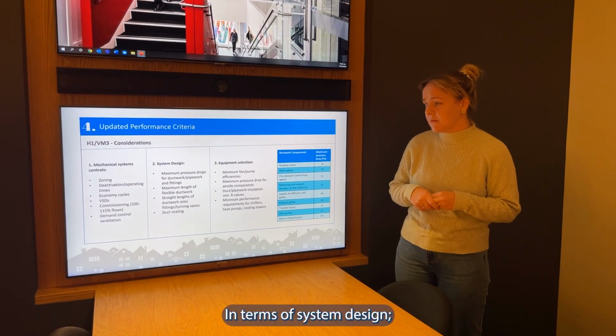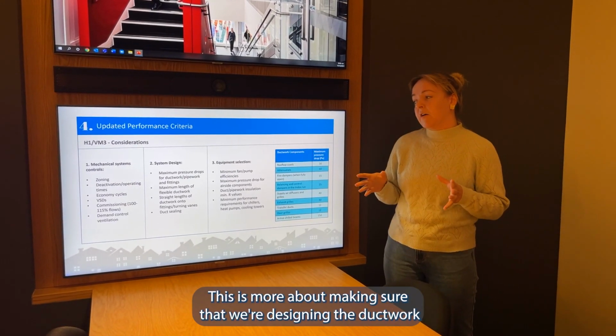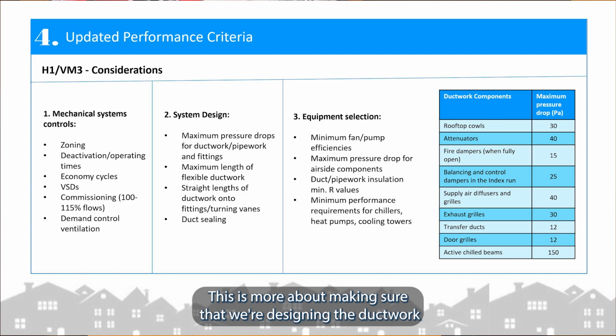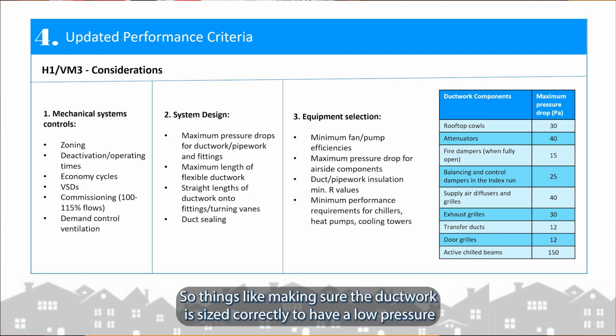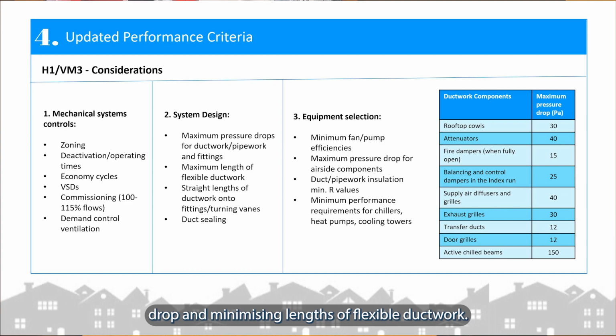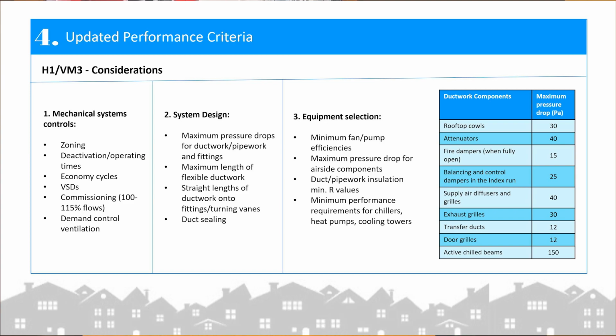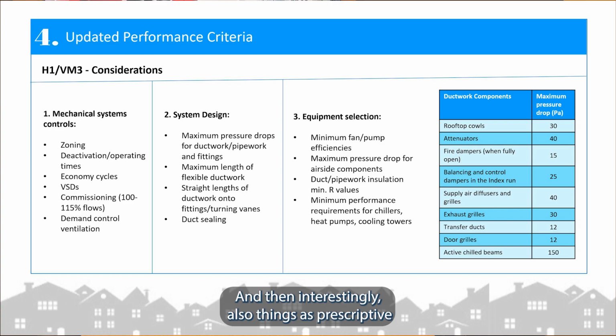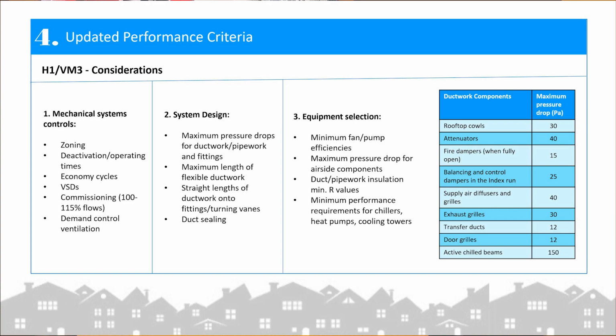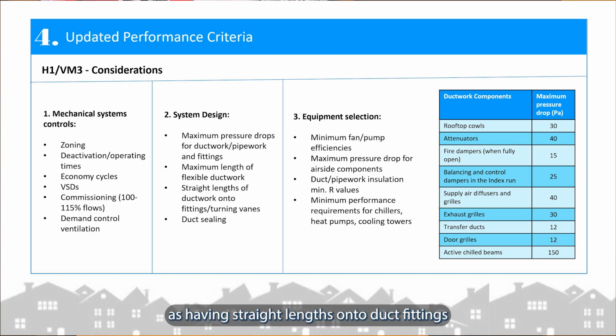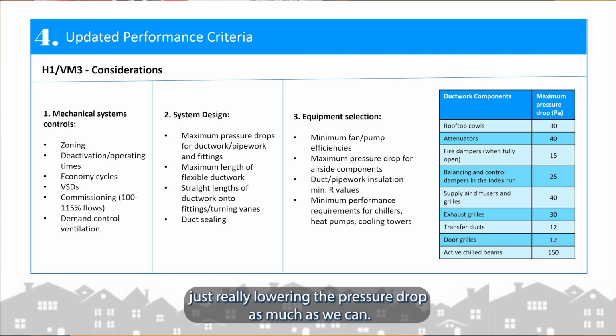In terms of system design, this is more about making sure that we're designing the ductwork layouts and things to have as low a pressure drop as possible. So things like making sure the ductwork is sized correctly to have a low pressure drop, minimising lengths of flexible ductwork, and then interestingly also things prescriptive as having straight lengths onto duct fittings and equipment to make sure that we're just really lowering the pressure drop as much as we can.